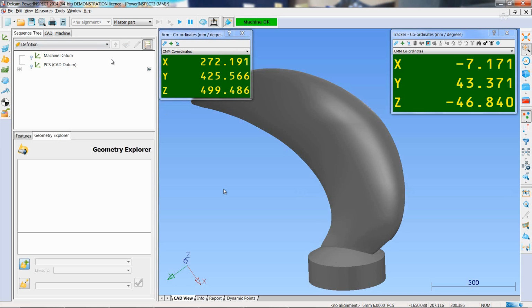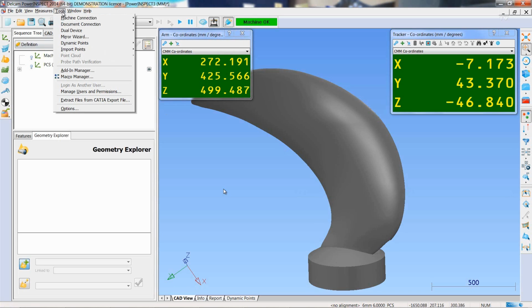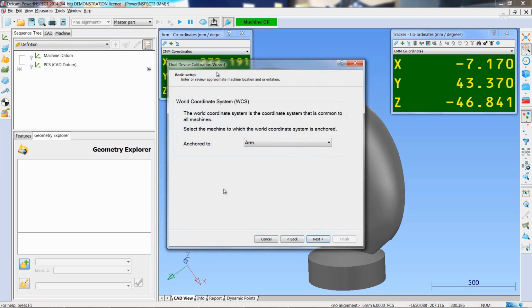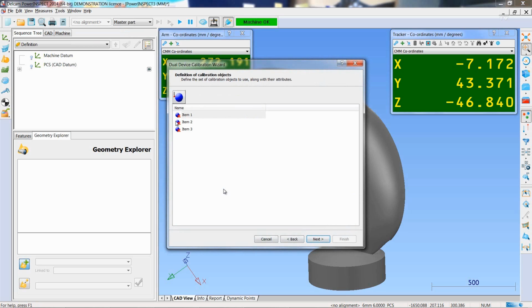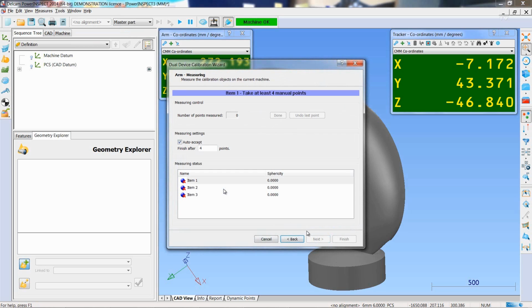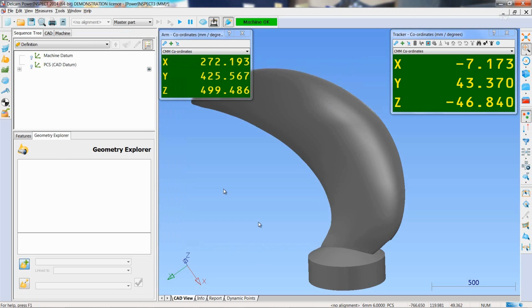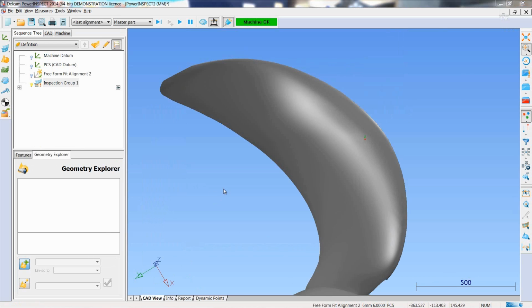That's fantastic. So if we go to tools now, to the dual device section, we see machine position calibration. We need to configure the position of the 2 devices through 3 calibration spheres, and by following this wizard we can easily configure the position of the 2 devices.